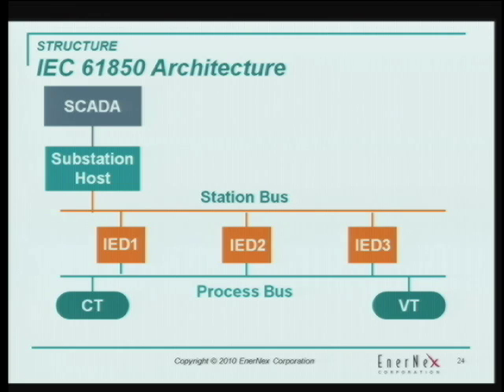In a typical substation, intelligent electronic devices are connected to generally two buses: a station bus used for polling and reading data from these devices, controlling them, opening and closing breakers, reading settings back, changing protective relay settings; and a fast bus, the process bus, that may be receiving high-speed sampling from voltage and current sensors in real time, driving the way the sensors and IEDs work.